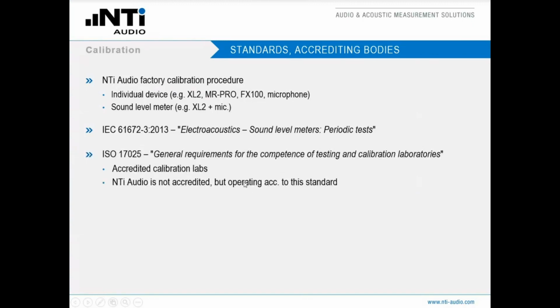Then there is another standard, the so-called ISO 17025, which refers to the calibration laboratories. So if you are looking for an accredited calibration lab, make sure that it complies to the ISO 17025. One question that is forwarded to us many times is whether we as NTI Audio are accredited. The answer is no, for different reasons, but we do follow the procedures defined in this standard. So we are maintaining a very high level, although we are not accredited.